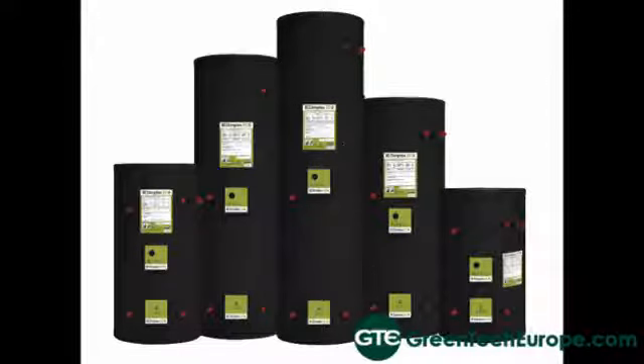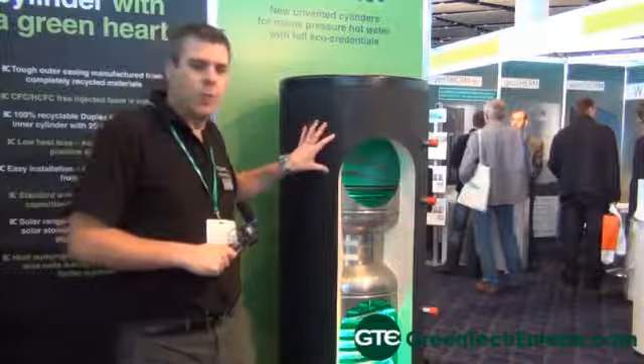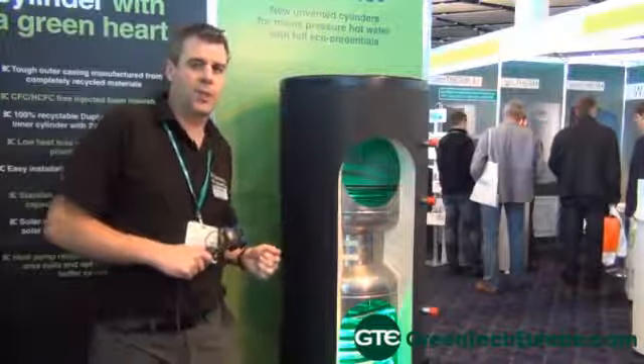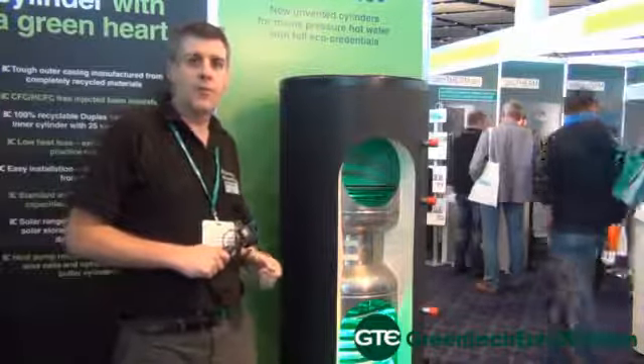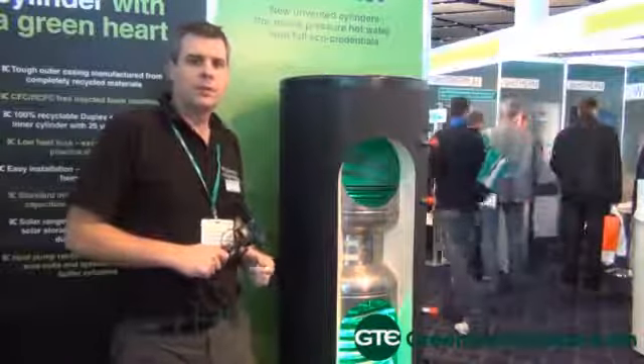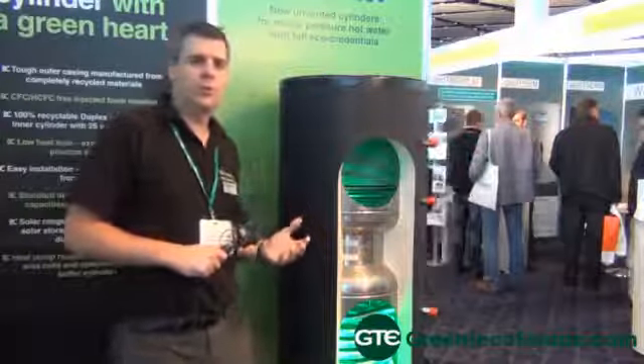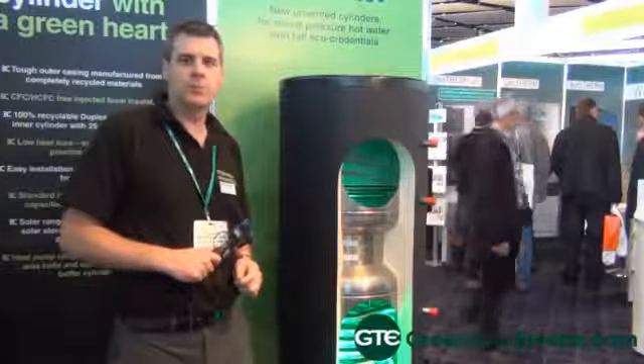Third, it has what we call a buffer tank, which provides specific support to the heat pump for defrosting and to get the best overall efficiency out of the system. What we try to do that's unique is piece these components together, so that the overall benefit to the customer is more than the sum of the individual parts.